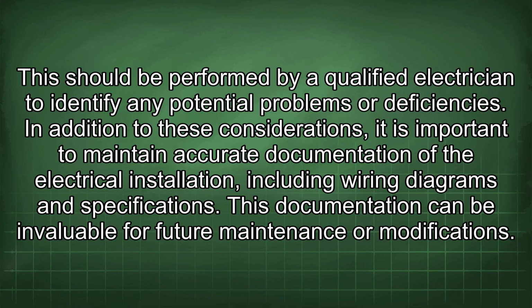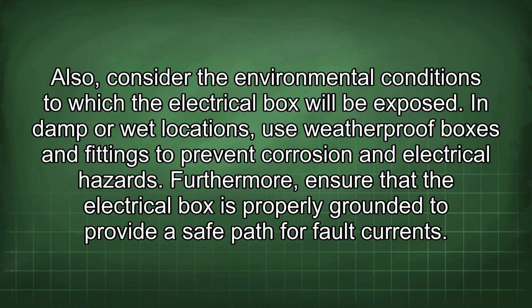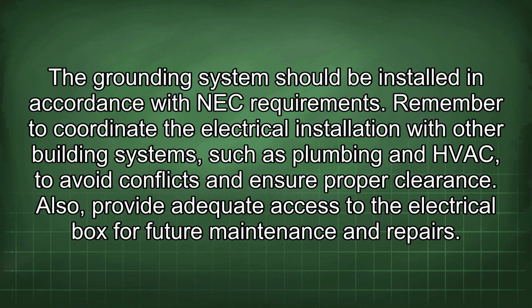In addition to these considerations, it is important to maintain accurate documentation of the electrical installation, including wiring diagrams and specifications. This documentation can be invaluable for future maintenance or modifications. Also, consider the environmental conditions to which the electrical box will be exposed. In damp or wet locations, use weatherproof boxes and fittings to prevent corrosion and electrical hazards. Furthermore, ensure that the electrical box is properly grounded to provide a safe path for fault currents. The grounding system should be installed in accordance with NEC requirements.